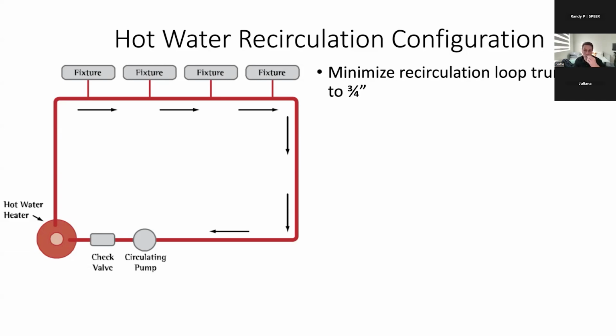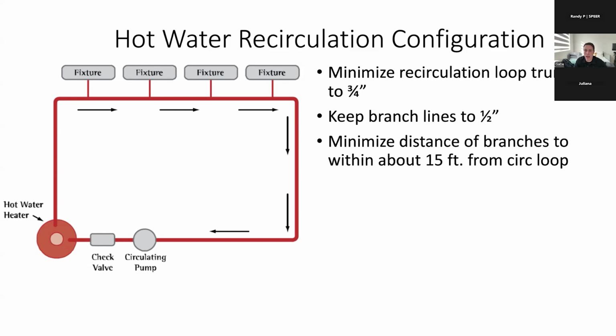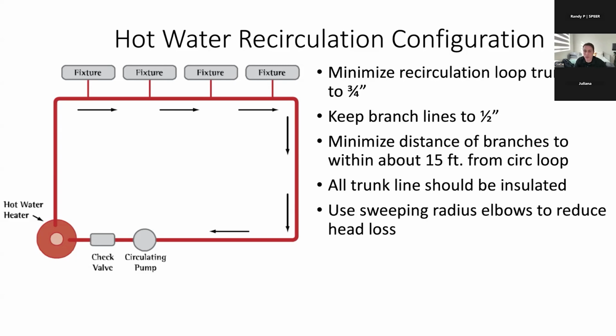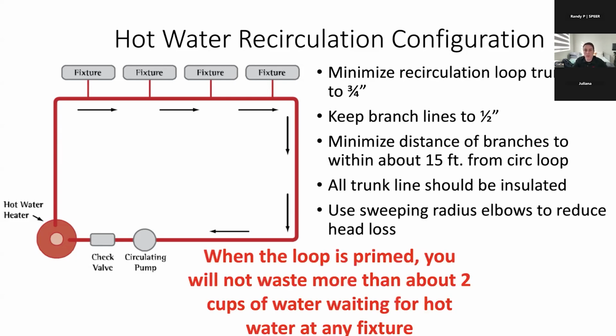So we recommend the loop be no more than 3/4 inch, and then you keep the branches to 1/2 inch. If you can keep the branches within about 15 feet of the main circ loop, and you insulate all of the trunk line, and make sure that you use sweeping radius elbows versus hard 90 elbows, because every 90-degree elbow in a plumbing system is the equivalent of adding 3 extra feet of piping from a head loss standpoint. If you take all of these things into consideration in your plumbing design, when the loop is primed, you'll never waste more than about 2 cups of water waiting for hot water at any fixture.